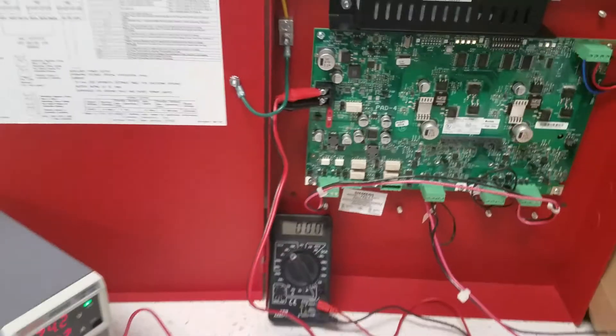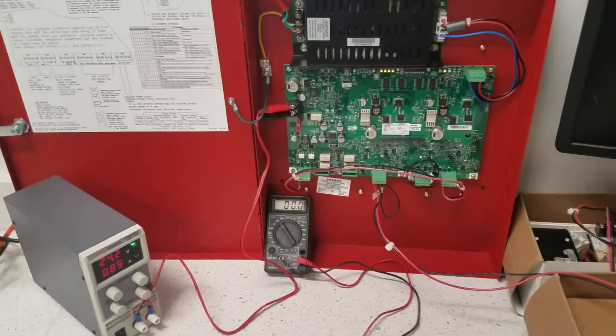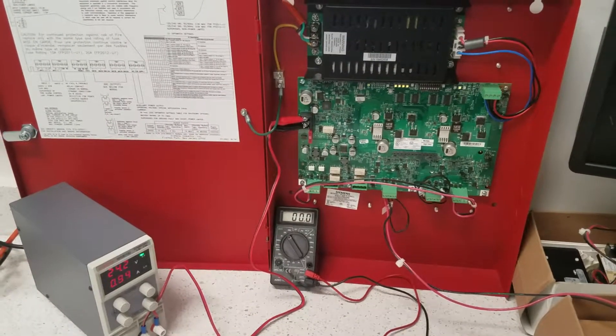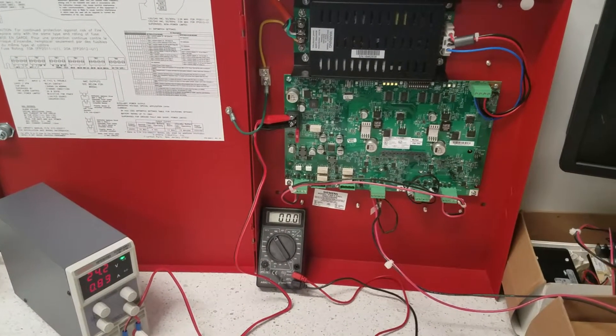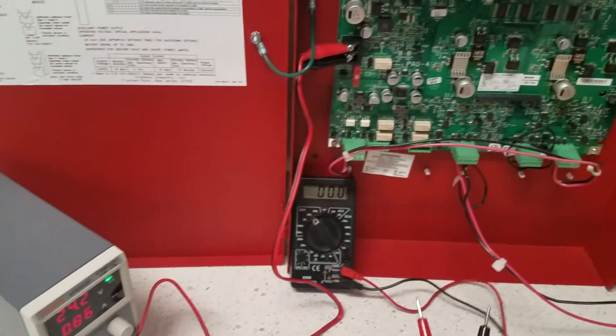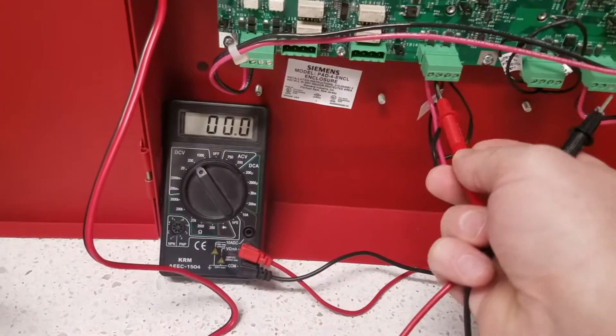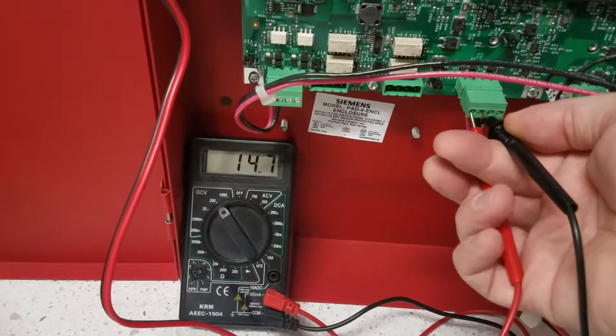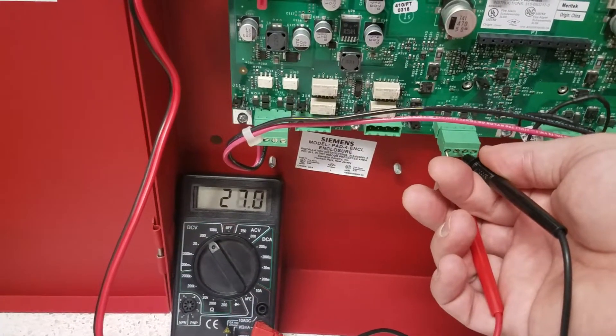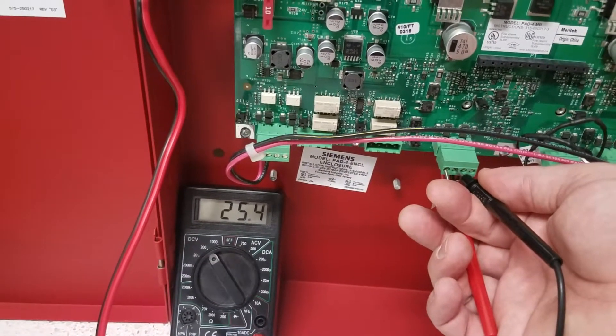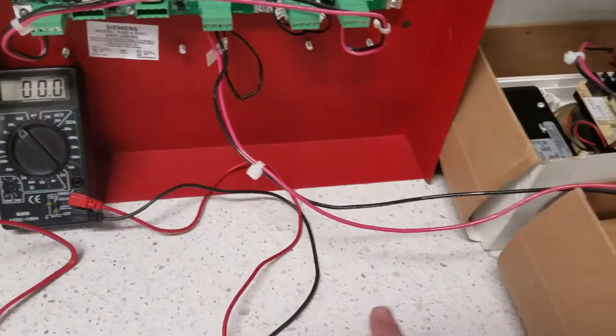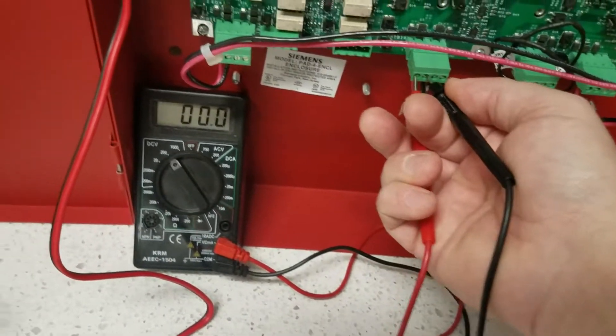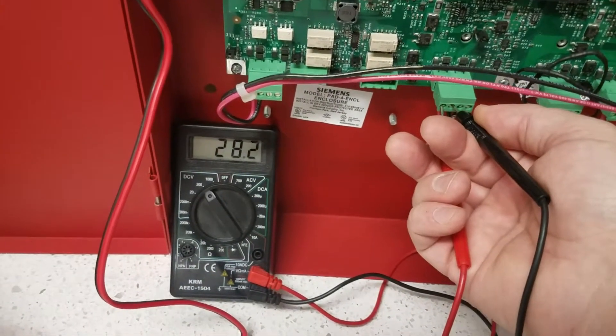Now, the question you have is what is this power boost circuit? The power boost circuit literally goes through and it ensures that it is putting out a minimum of 24 volts at the notification circuits, at the terminals. So let's go through and let's measure the terminals. As you can see, I'm getting 27, 28 volts out of the terminals. And this is to the notification circuit. As you can see, the wiring is going to the devices, 28 volts.